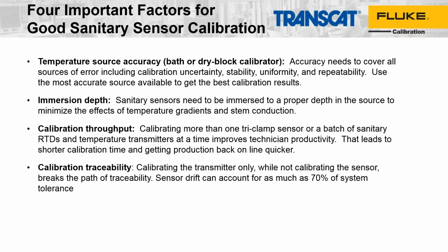Some other things to consider are things like immersion depth. One of the largest sources of error for a temperature measurement can be immersion effect, or error caused by the sensor not being sufficiently immersed into the measurement medium. And so having a proper amount of measurement depth can help remove these errors. And again, with tri-clamp or sanitary sensors, this can be a big challenge, because some of these, as you saw in some of the pictures, might only be 2 inches long, and with a lot of metal mass surrounding the temperature sensor. So we'll talk about that a bit more here over the next few slides. Calibration throughput is another concern.